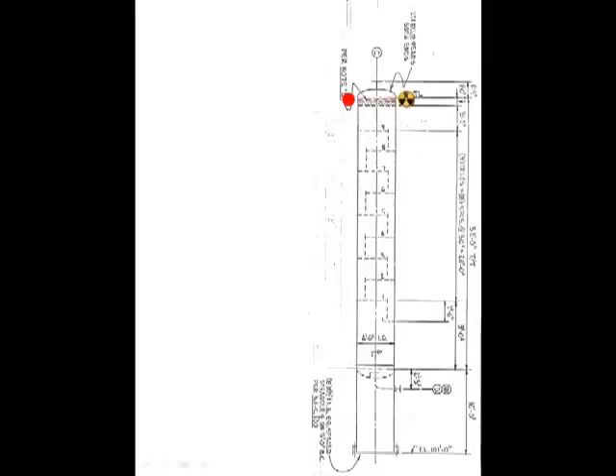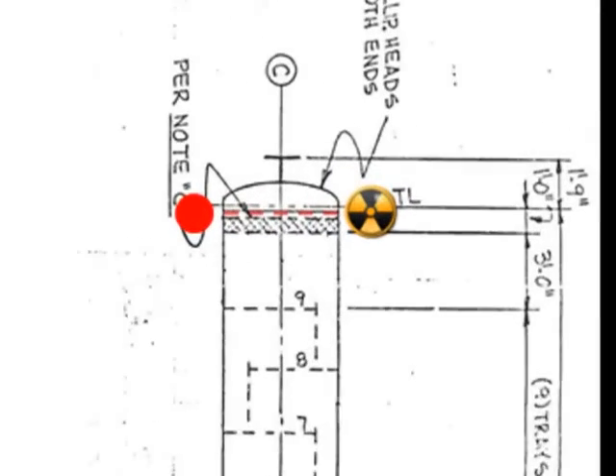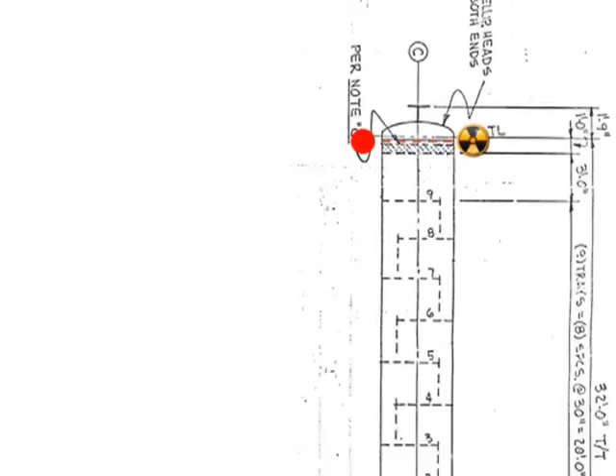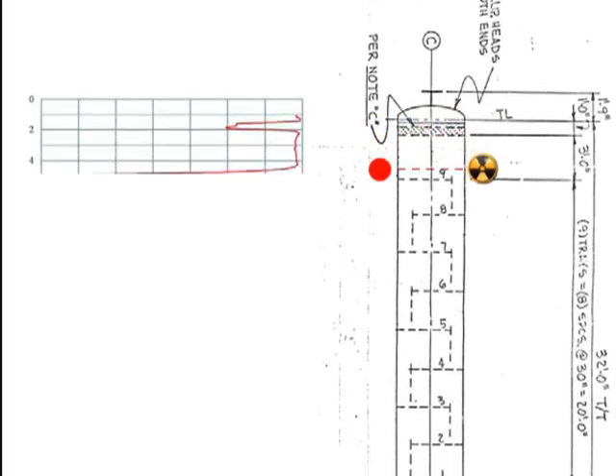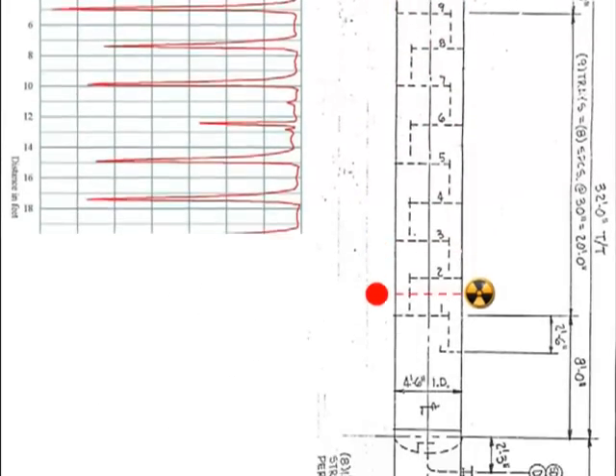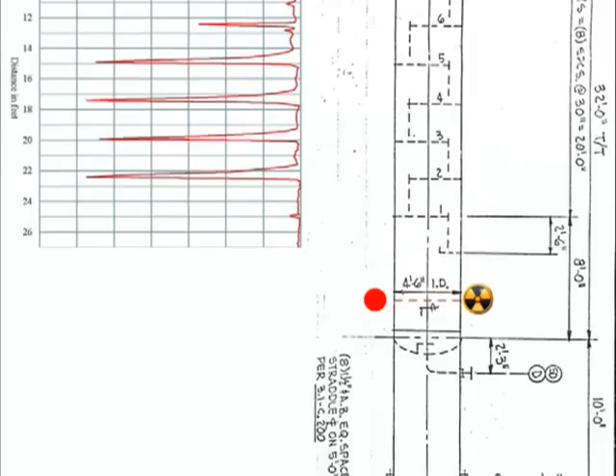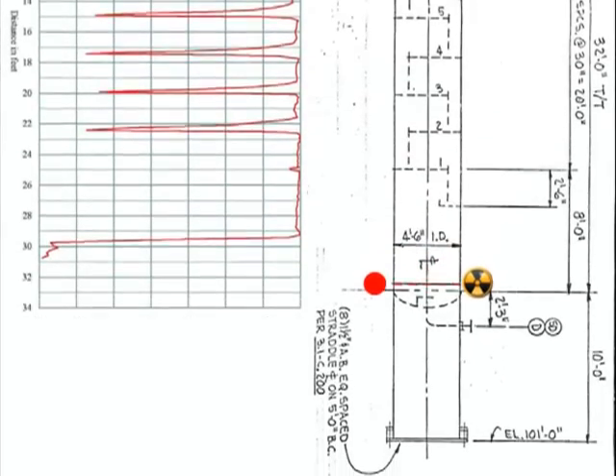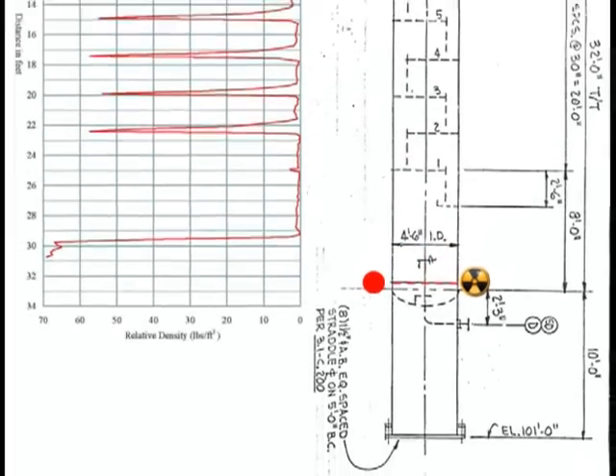This is an elevation view, also taken from the tower drawings, showing that the gamma scan started at the top tangent line, and the source and detector were lowered simultaneously down the tower to produce a density profile or a gamma scan profile.